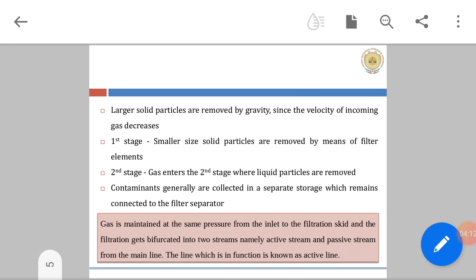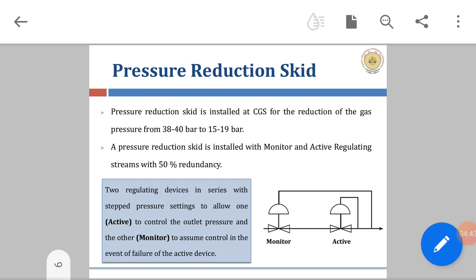We can understand in detail the pressure reduction skid. Pressure reduction skid is installed at CGS for the reduction of gas pressure from 38 to 40 bar to 15 to 19 bar. A pressure reduction skid is installed with monitor and active regulating streams with 50% redundancy, two regulating devices in series with stepped pressure setting to allow one to control the outlet pressure and the other is kept wide open to assume control in the event of failure of the active device.